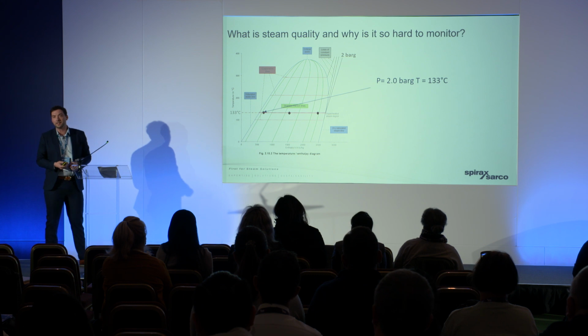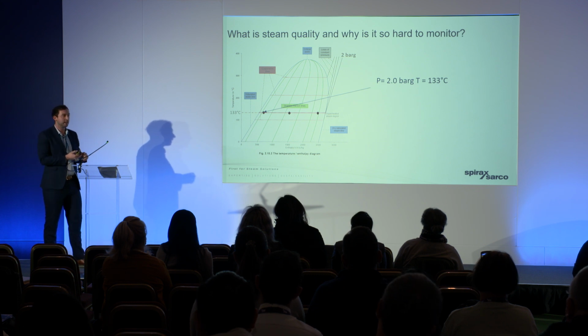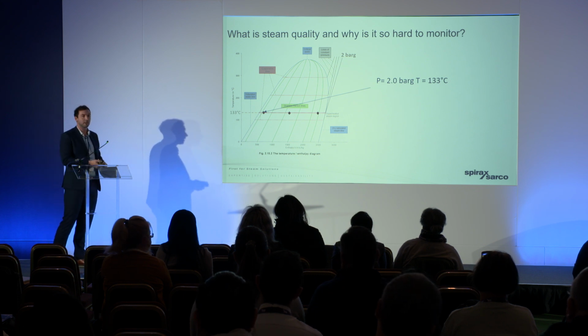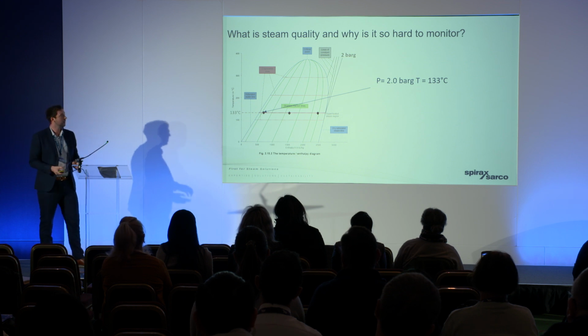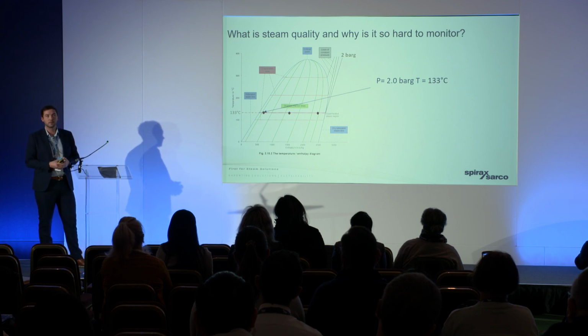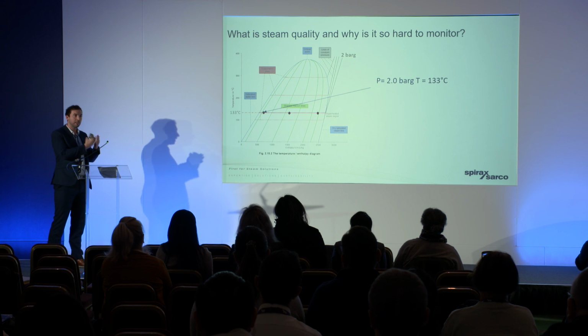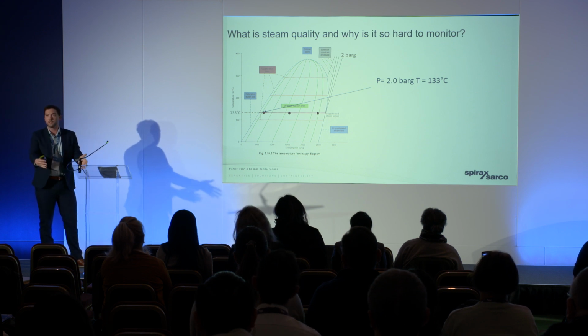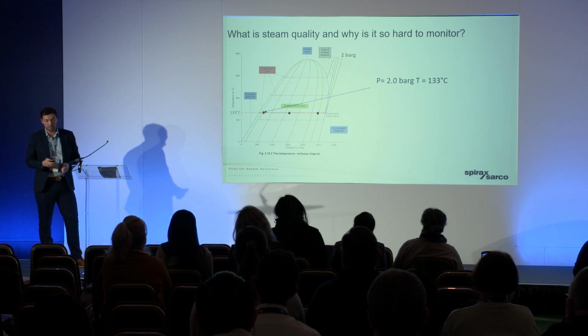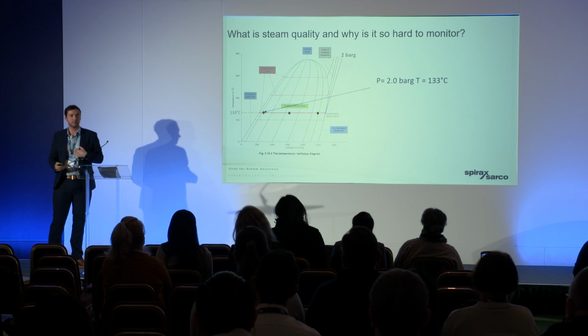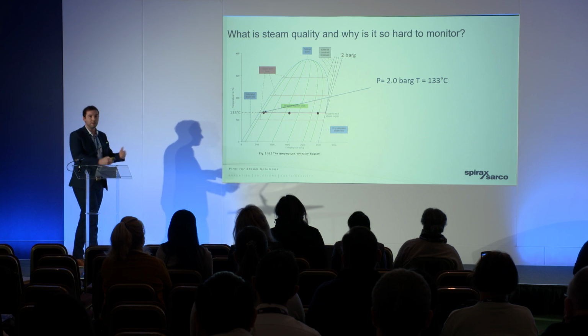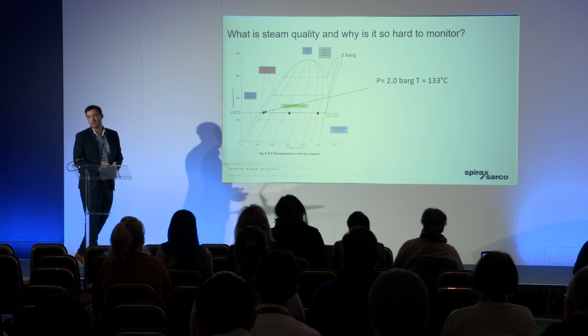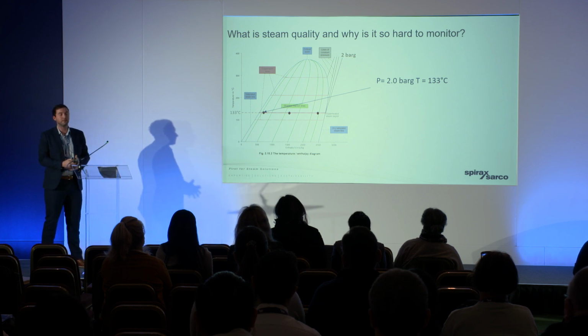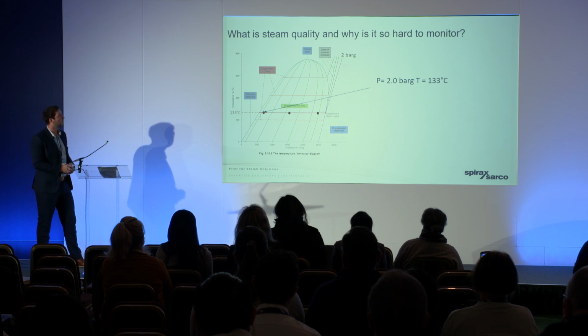It doesn't carry any water droplets with it. It's not carrying any contamination. It's not damaging our equipment. And as Chris mentioned, it's maximum heat transfer. Because as soon as that gas meets a cold surface, it's condensing, and it's giving up all of its energy as it turns back to a liquid. So our mission, really, Spirax's mission, is to ensure that every bit of steam that's generated is 100% a gas, because it's going to be the most effective heat transfer medium.